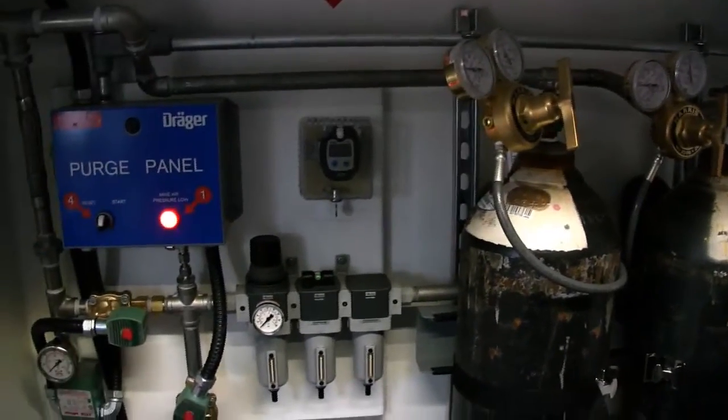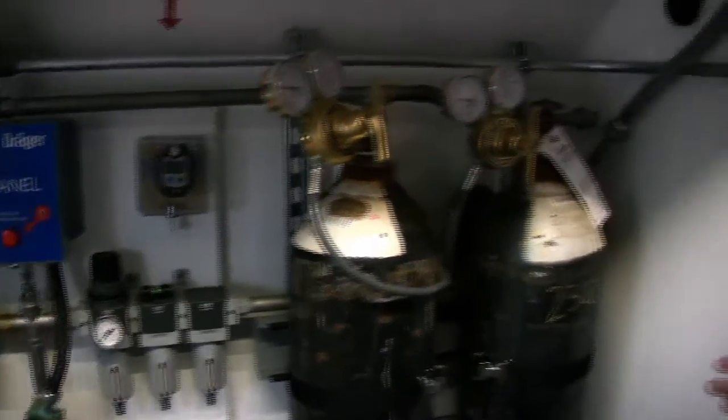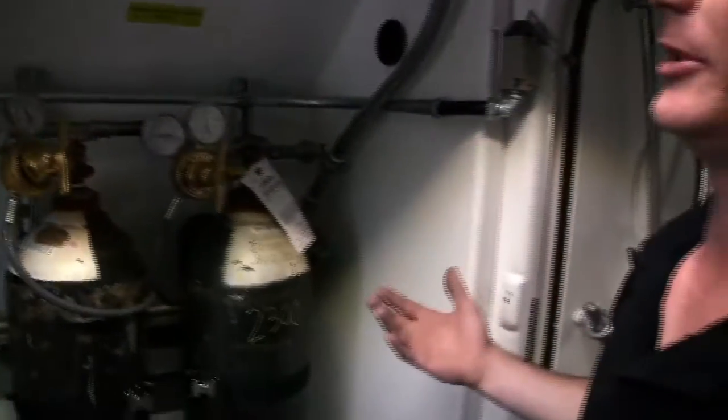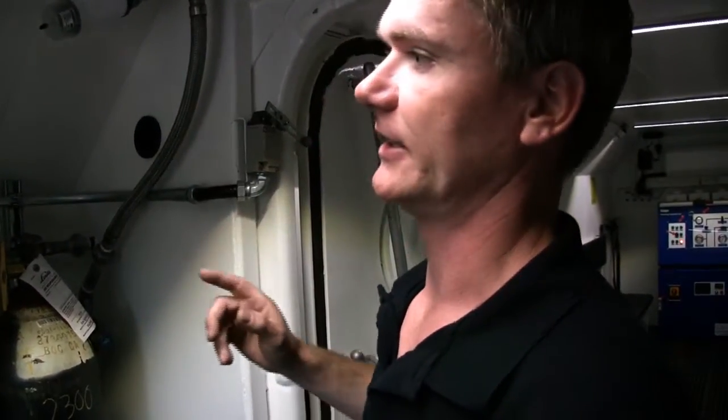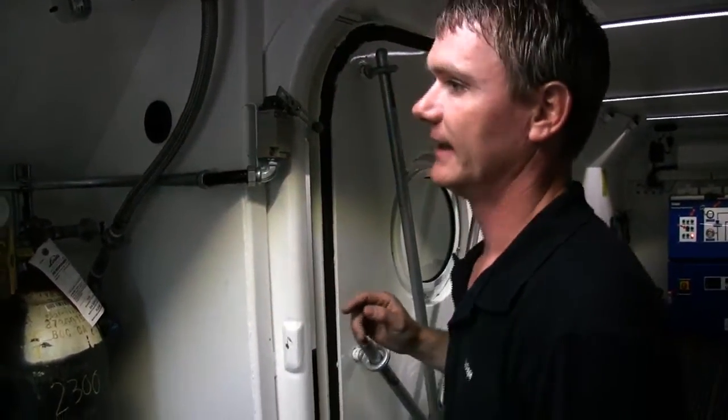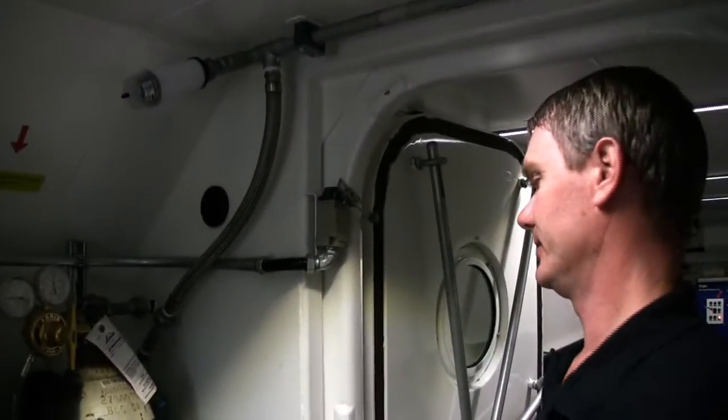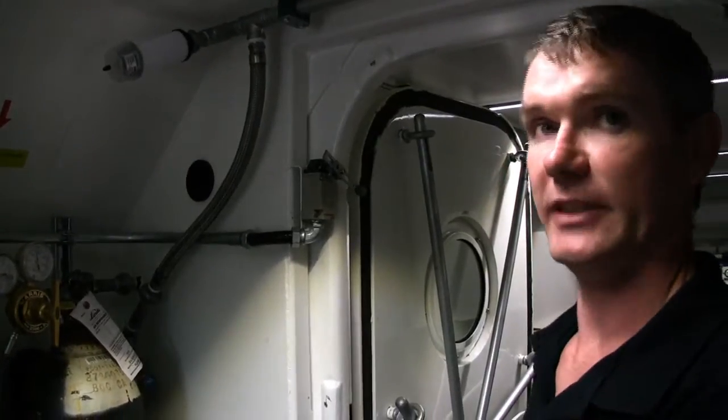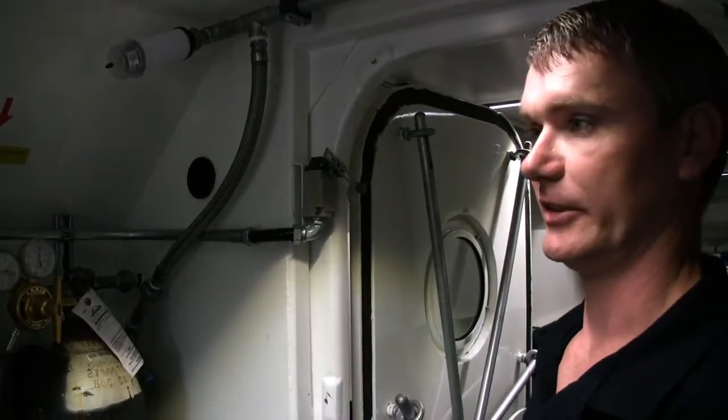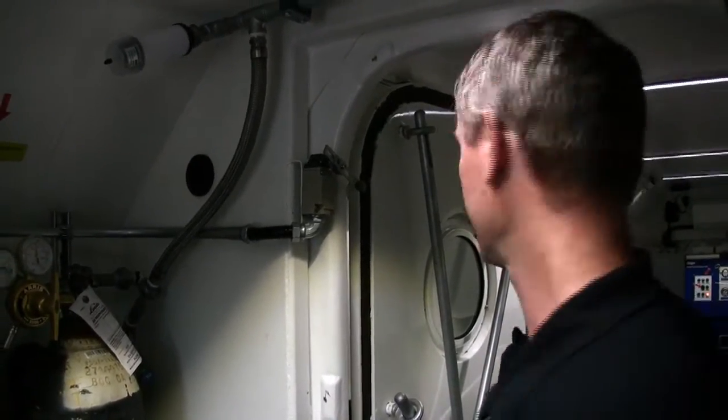I believe the Ontario standard for workplace is 25 ppm is the limit. However this is an emergency survival system. 100 ppm is safe. Not for extended periods of time. So this is a monitor alarm just to tell you what's going on. Give you an indication what's happening. And with a small volume here if you have less than 100 ppm going through into the main chamber would be okay. It's going to dilute itself down.